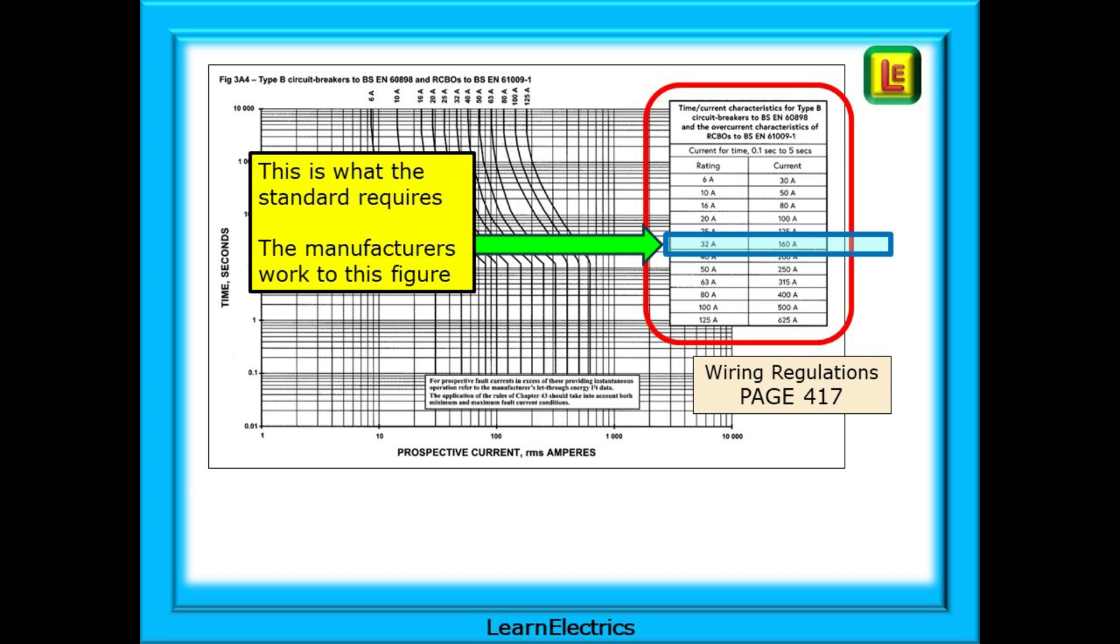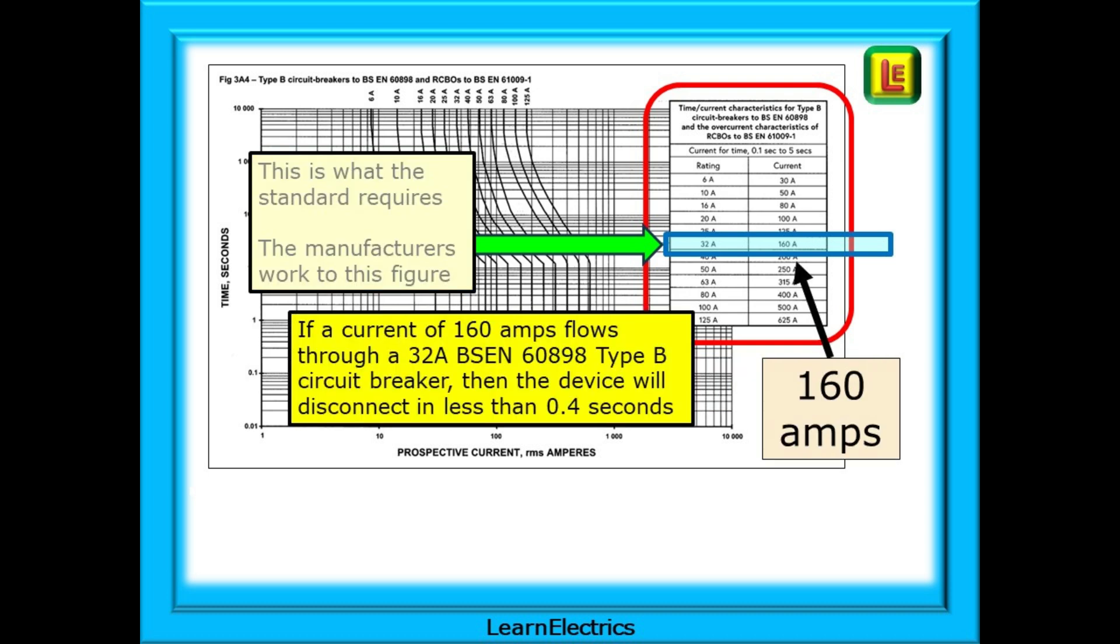This is the requirement that manufacturers will make circuit breakers to, how they design them. This is the starting point for calculating ZS. If a current of 160 amps flows through a 32 amp BS EN 60898 type B circuit breaker then the device will disconnect in less than 0.4 seconds.